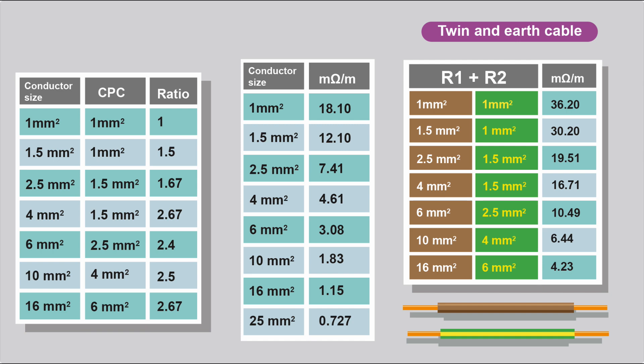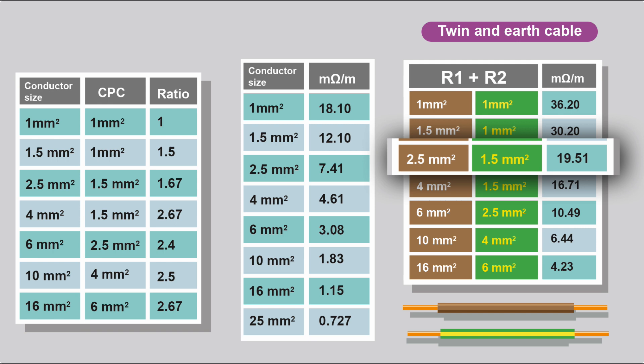If you recall before, the 2.5mm-squared conductor had a milliohms per metre rating of 7.41. We go to the same 2.5mm-squared conductor here. When it's combined with the 1.5mm-squared conductor, the CPC, we get a milliohms per metre value of 19.51.